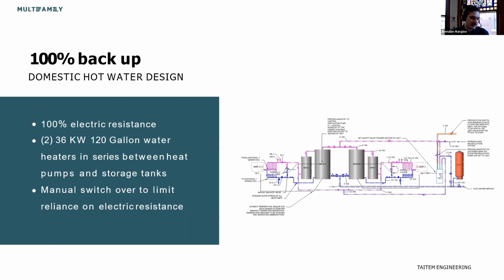If we need to switch over to electric resistance, you would deactivate the central heat pumps. You would isolate them, drain the system of all the water, and then open up some ball valves and turn on power to the water heater and a circulator pump. And then we would have a 1-for-1 replacement until the heat pumps came back on. We wanted to make that a fully manual switchover, so it was intentional. We didn't want anybody to flip this on because they thought it should be on. There's a process that needs to happen to completely switch this over.